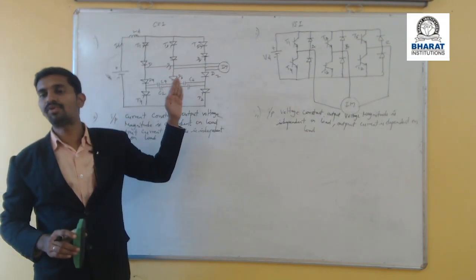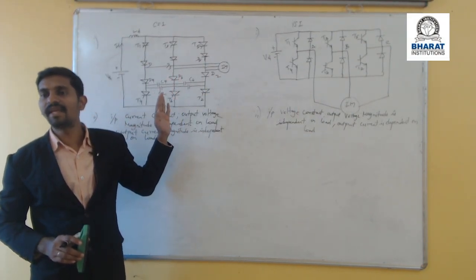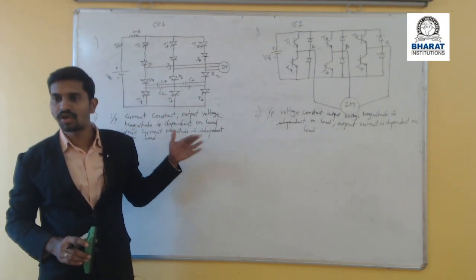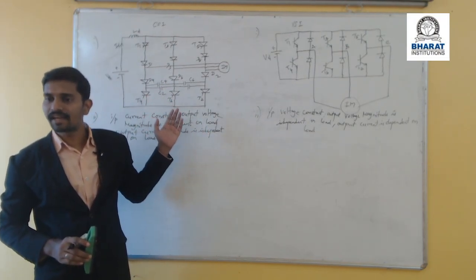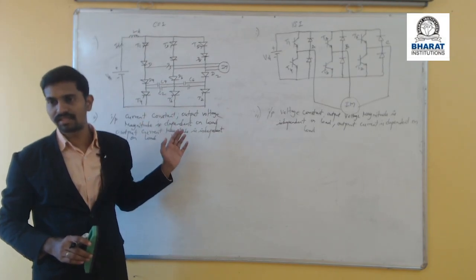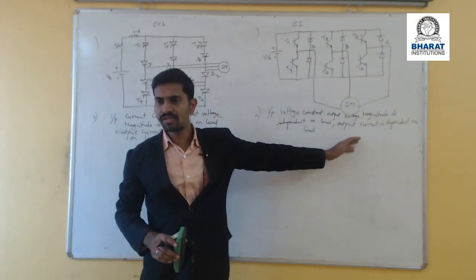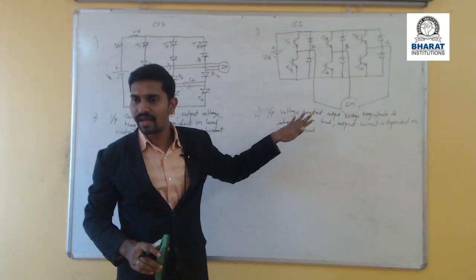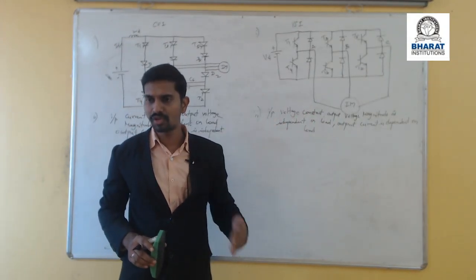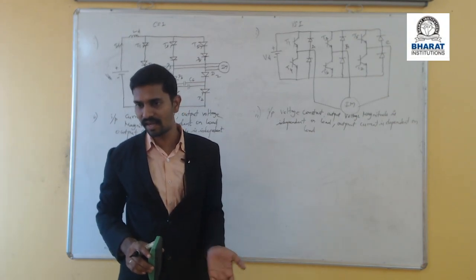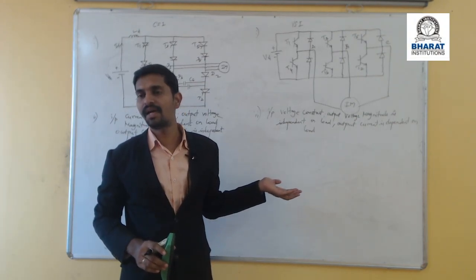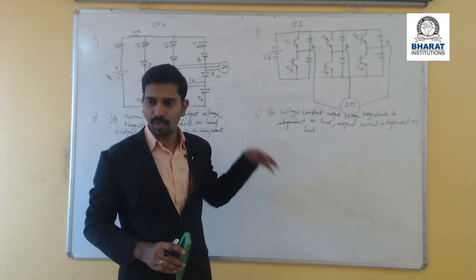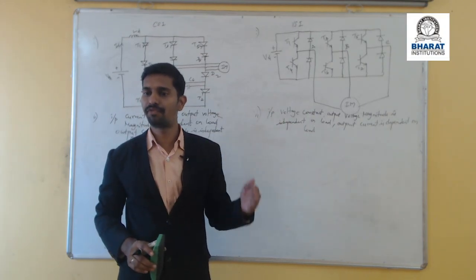Because of this input inductance in CSI, the circuit is protected, so no extra fuse or switching devices are required. But in voltage source inverters, there is no input inductance, so we require fuses or protecting devices to protect the device from high current or any fault.